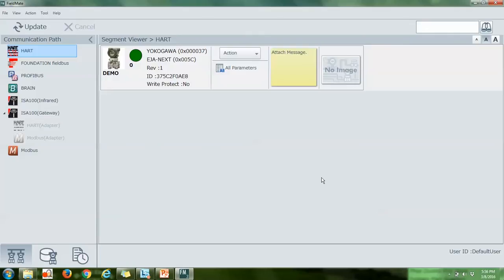So I just opened up Fieldmate, and it already recognizes the transmitter that I have connected. Its tag is Demo, so that's what it's showing here. It's showing a little icon of the transmitter, so I know it's an EJA. We've got a little indicator light, like a stoplight, and right now it's reading green, so everything's good. If there were some error messages, it would give either a yellow light or a red light. Yellow would be not so critical errors, and red would be a critical error, like something's wrong with the sensor, or something severe has happened. Then we have some identification information about the transmitter: the vendor ID, Yokogawa, the model, so EJA Next or EJA, what revision it is, what the unique device ID is, and whether or not the write protect switch has been turned on.